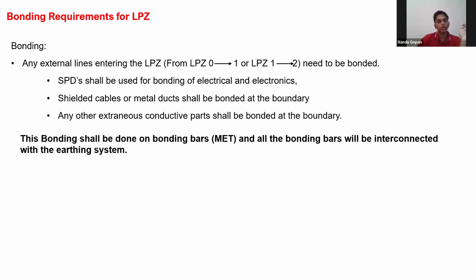For this bonding, you don't need anything elaborate - you can just bond it to a MET, meaning a bus bar. You don't need sophisticated equipment; you can go to the market and get a stainless steel or copper bus bar, cut it, and do the bonding. The minimum size for this bonding bar is set in the standard, so you can just refer to it and follow that size - it's more than enough.